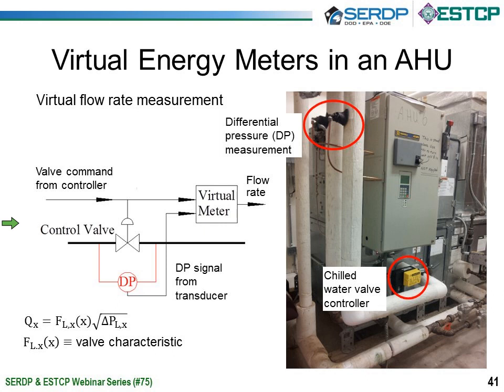We determine F through a training process or calibration process in which we measure the pressure difference, we measure the flow rate using a temporarily installed sensor, in this case, well, I'll show you this in just a minute. I'll show you the sensor in a minute, to determine this function F of X. We then, after training, put F in there, we measure delta P, and for each delta P, we then can calculate a virtual value of Q.